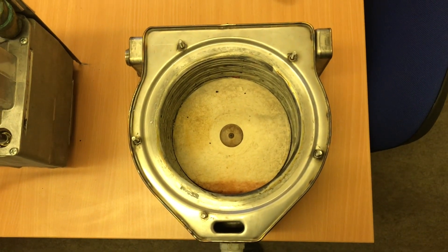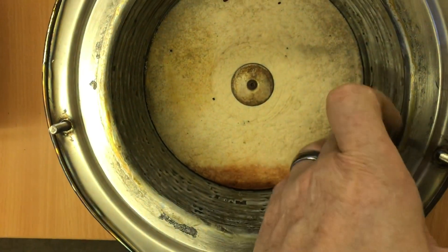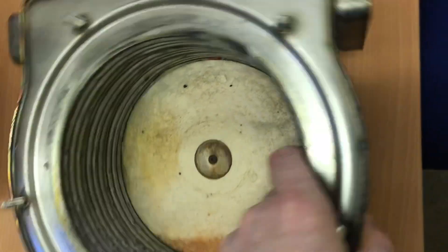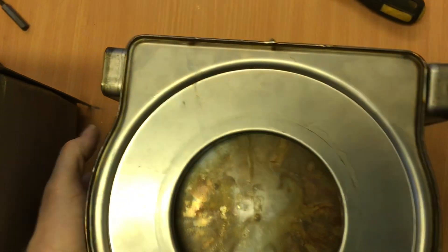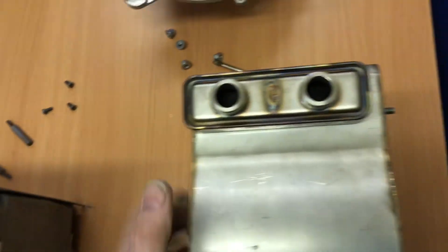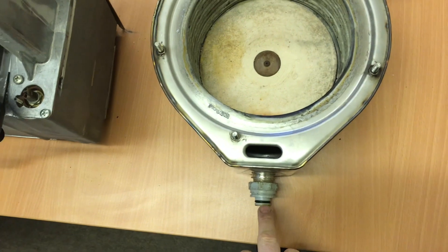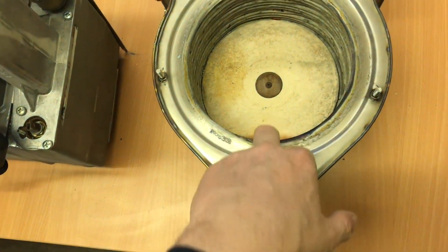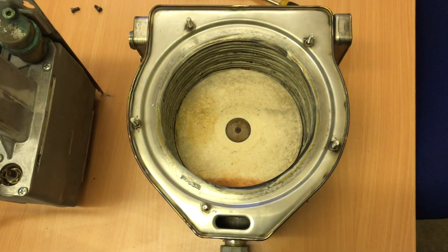Next is the stainless steel heat exchanger — the Giannoni heat exchanger. You can see it's made of coils of 10mm stainless steel pipe. There are actually two coils for the flow and return. Heat burns 360 degrees, going down through the bottom, and products of combustion come out of the back and up through the top. The outlet is plastic because all the heat has been extracted by the large surface area. At the bottom is a condensate trap where you can observe the condensate.